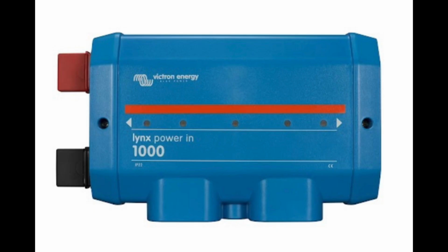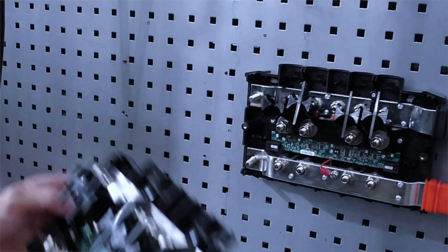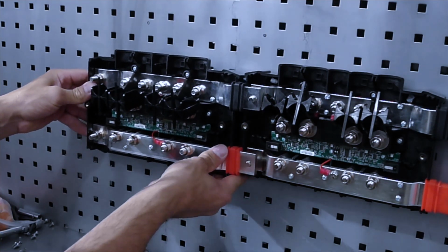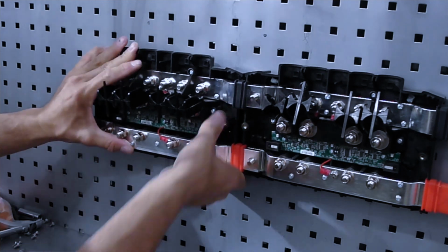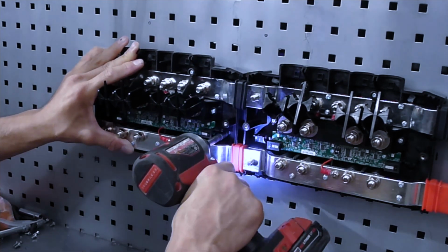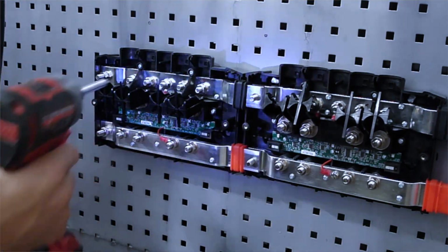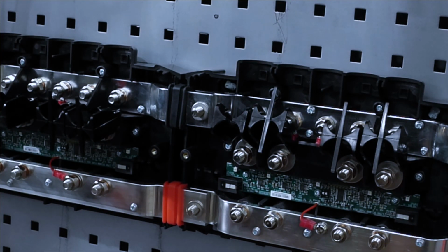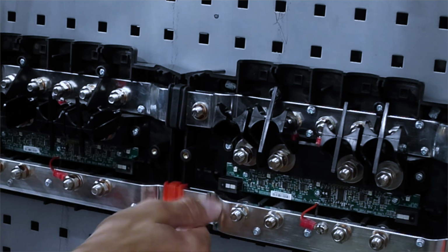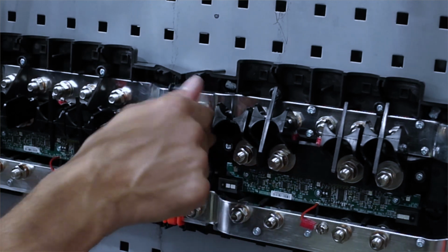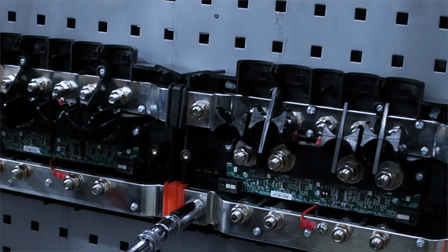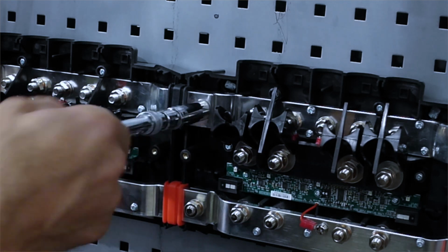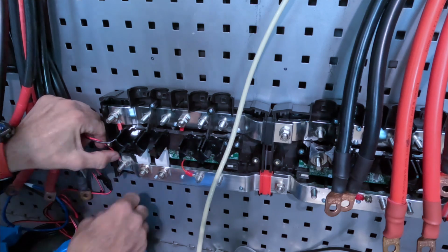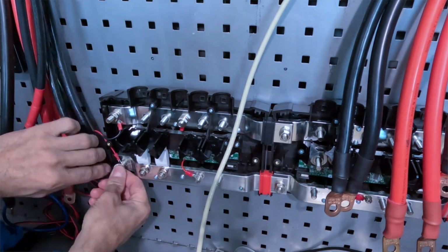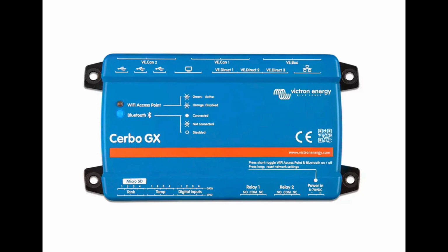This is the Victron Energy Lynx distributor. This unit is actually very impressive. It is a little bit expensive, but everything happens for a reason, right? This is a DC bus bar where we can connect up to 4 DC fuses, and the Lynx will monitor the status of each fuse, indicating the condition via LED on the front of the unit. The bus bars are rated for 1000 amps, multiple units can be connected together, and able to send all the data to the Cerbo GX. These tiny cables I'm connecting right now are the power cables for the Cerbo GX.